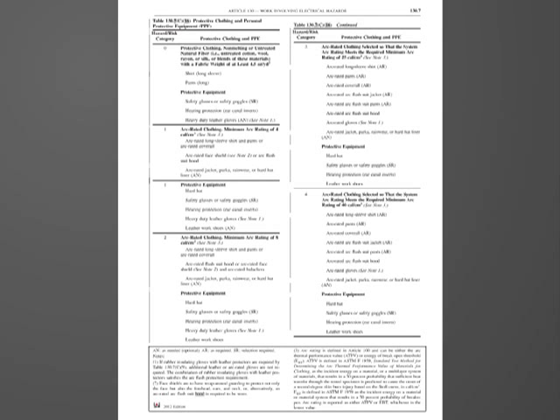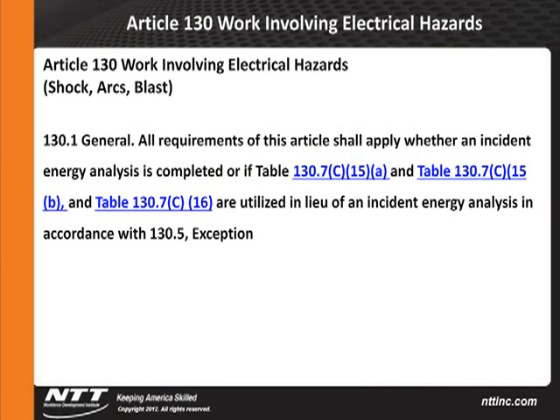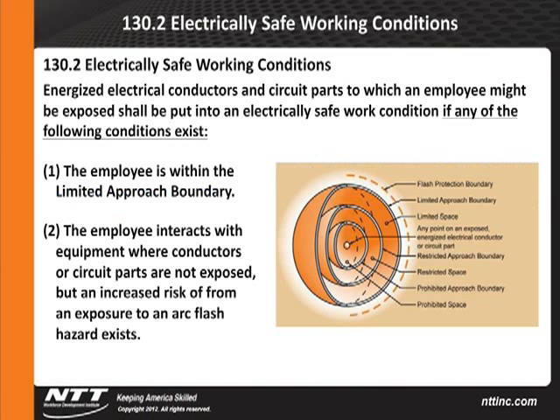So let's go back to the slide presentation. Give it a second to come back to where we're at. When we talk about electrical safety work practices, out of Section 130.2, there's some new language. Energized electrical conductors and circuit parts to which an employee might be exposed shall be put into an electrically safe condition if any of the following conditions exist. The employee is within the limited approach boundary. The limited approach boundary basically says if I'm within a certain dimension of an exposed part, or the employee interacts with the equipment where the conductors or circuit parts are not exposed, but an increased risk of exposure to an arc flash hazard exists.